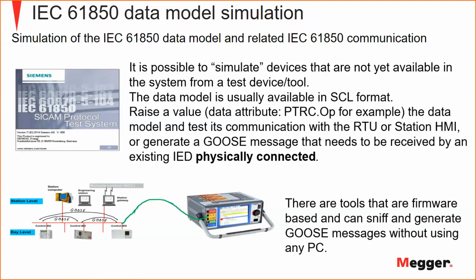And these tests are very important for interoperability tests. You have 2 relays from 2 different manufacturers. Manufacturer A is available because you are manufacturer A. Manufacturer B is not available yet. It will come in the substation, but you are not in the substation. You want to simulate manufacturer B sending the GOOSE message that you will receive, without having it there. And you don't care if manufacturer B will really trip or will not trip. You want to simulate the GOOSE messages because you want to verify your own configuration and settings. So there is a big benefit in this data model simulation.